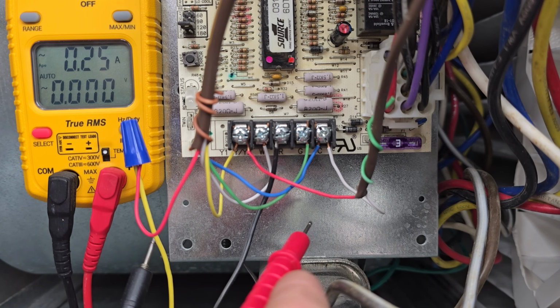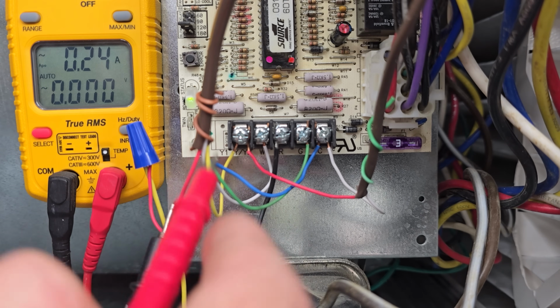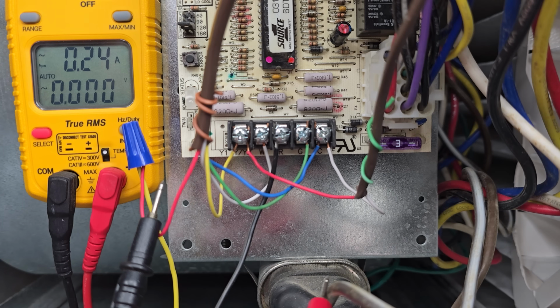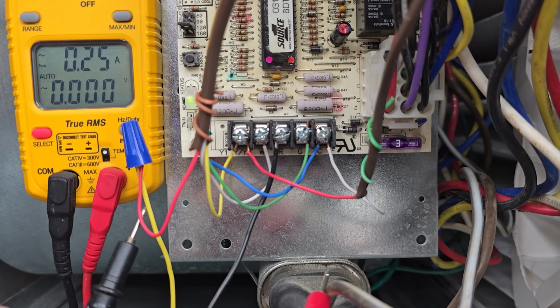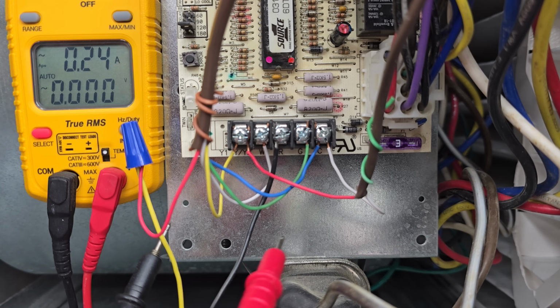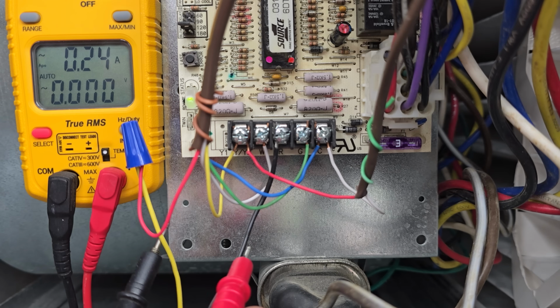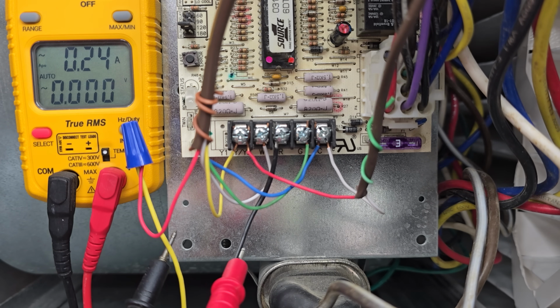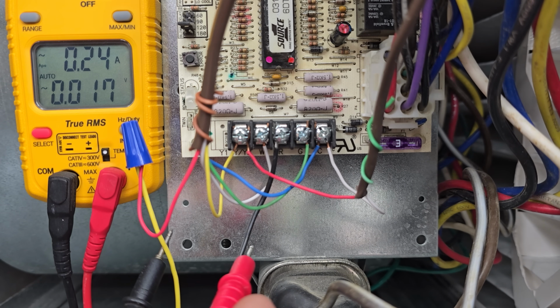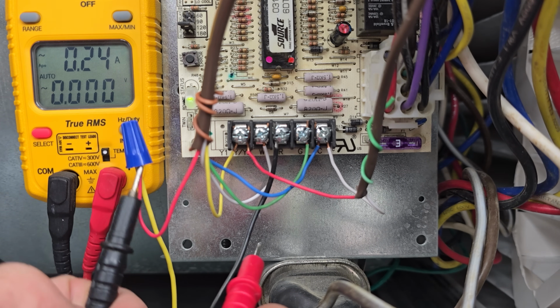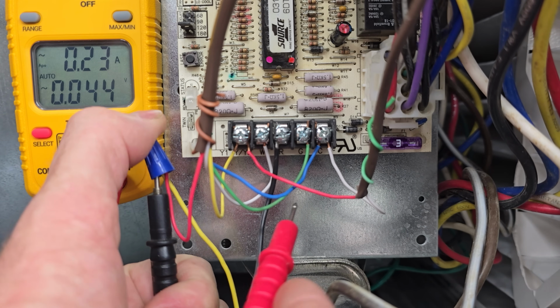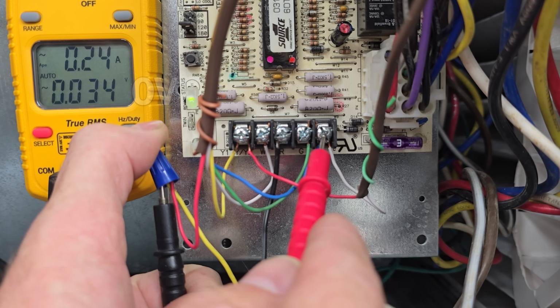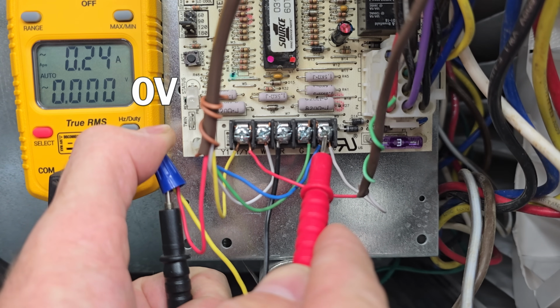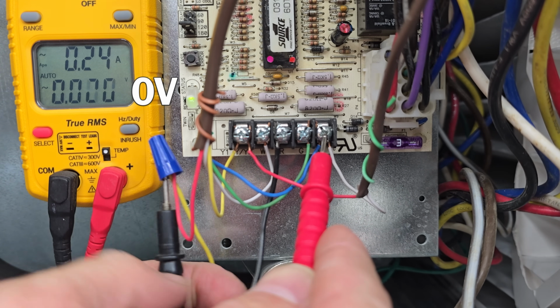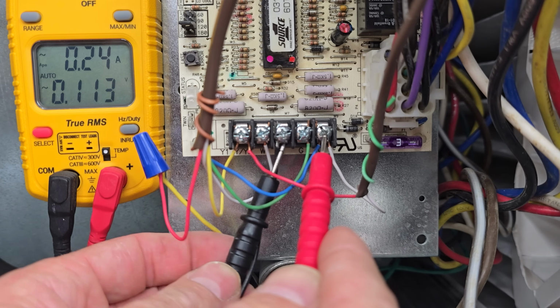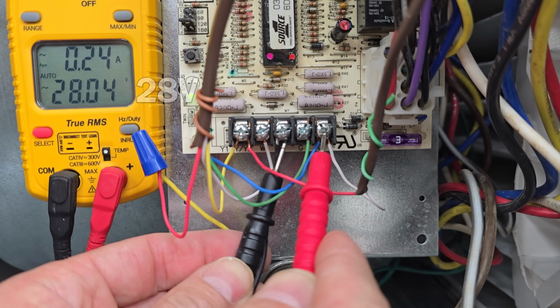So you see that we have this wire bundle right here going to your thermostat. And this red wire is leading to a yellow wire. So these two wires are leading to 3 condensate safety switches that are wired in series. And so one of those must be broken. So if we measured up inside this wire nut here to common, you can tell that our power is being broken in those switches somewhere. So we got 28 volts there.